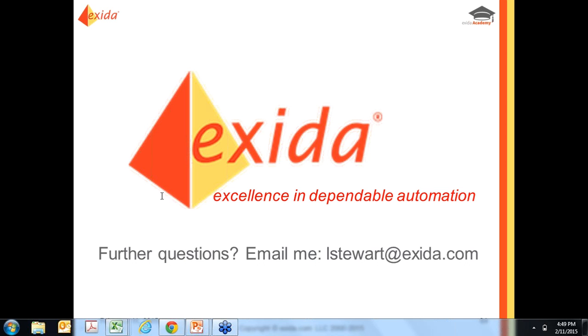The next question: for a low demand application, the risk reduction factor is equal to 1 divided by the PFD average. So how do you obtain the risk reduction for high demand applications? That equation is in the standard, and it's one of the tables that we showed earlier. If you need to see that table, I can send that to you if you'd like me to email that to you.